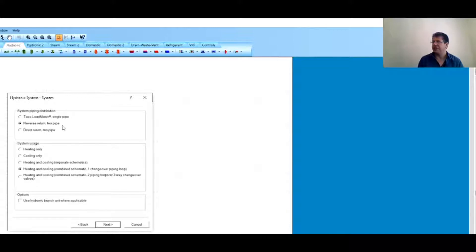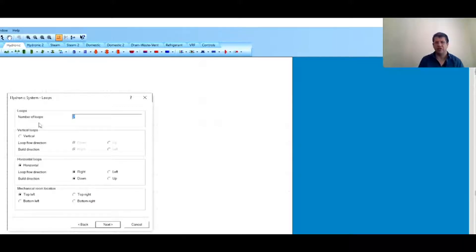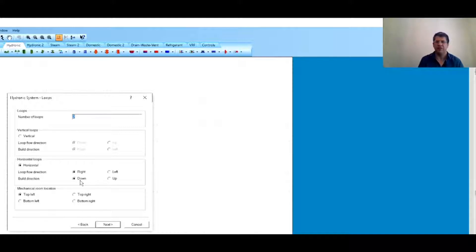Now I'll go to the Insert tab, then the Wizard, select Hydronic System, and go to Next. I select reverse return as the piping type. I'll have heating and cooling combined as a one-changeover system — essentially a two-pipe fan coil unit with either heating or cooling. I have a two-story building so I want two loops running across the corridor. The build direction is downward, meaning the pipe drops from the loop down to the fan coil units.